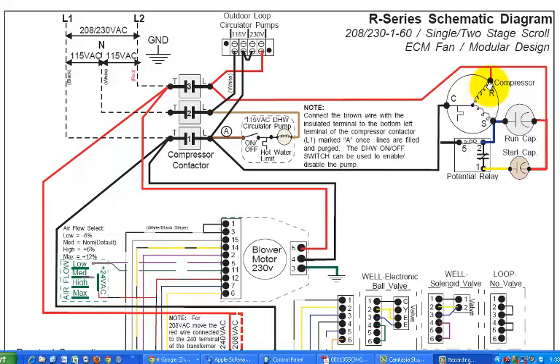So the switching action then of that compressor contactor is real important. If it doesn't get switched, then of course power doesn't get delivered to the compressor and nothing's going to happen with it. Now, as well as feeding the compressor, we'll see that these lines are coming over and feeding the run and the start capacitor, and that the potential relay is actually triggered by that as well. It's also seeing the voltage showing up there. We're going to leave those for a second. They are in place to help the compressor do its thing, but without getting into too much detail right at this point, we just want to focus on the idea of the schematics.